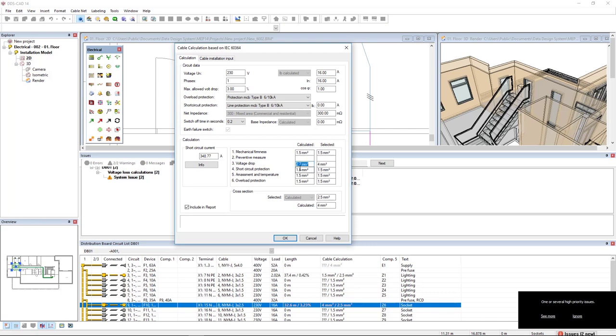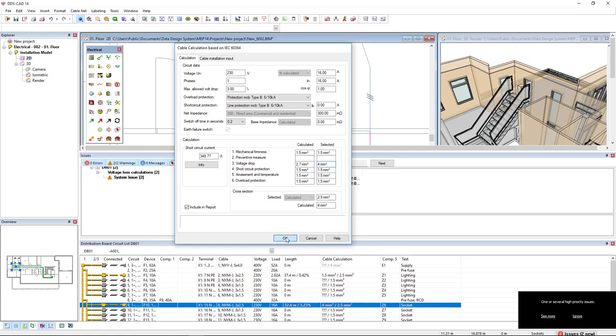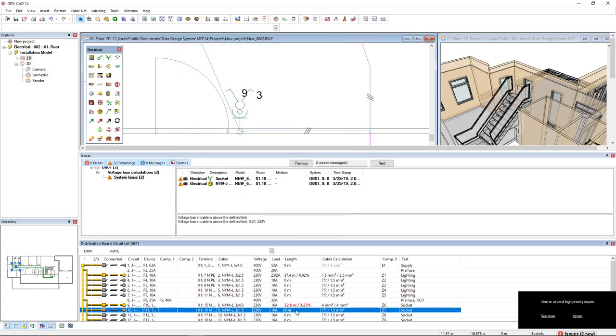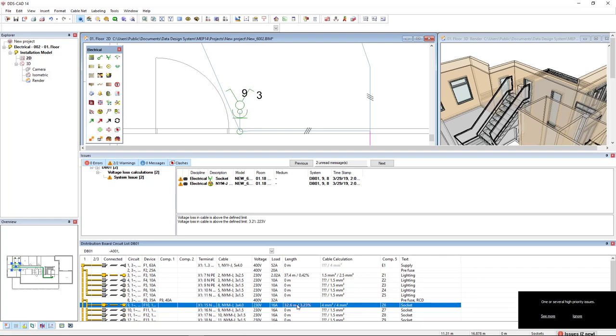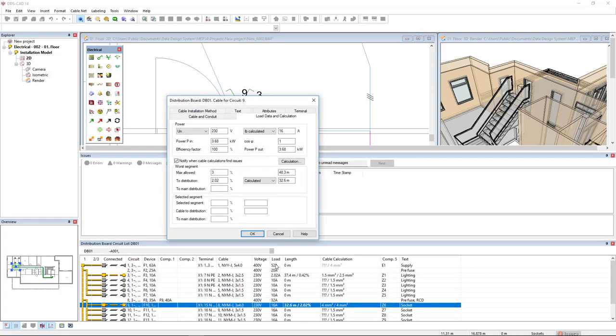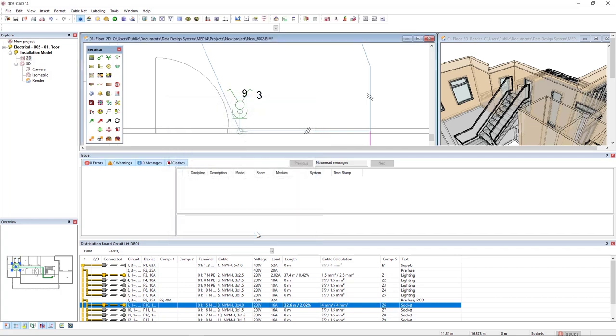It's calculated 2.7, but as we don't have this cable size available, it selected the higher, in this case 4 square millimeters. I will click OK and DDSCAD will automatically redimension the cable size. I will double click now the length column in this circuit and we see the voltage drop has also been updated. The issue has been automatically removed.